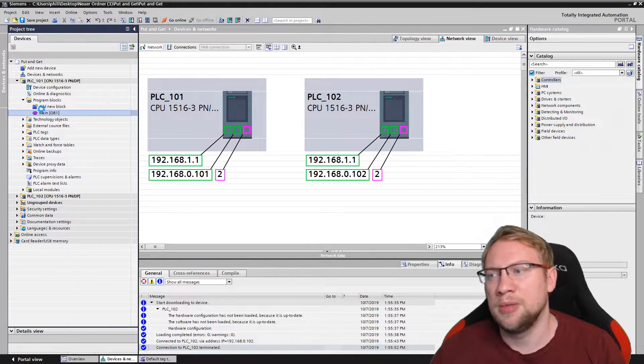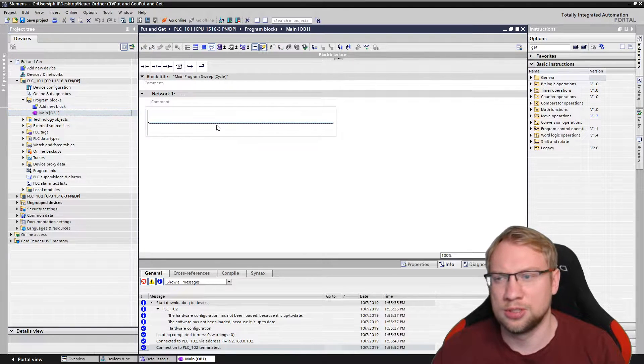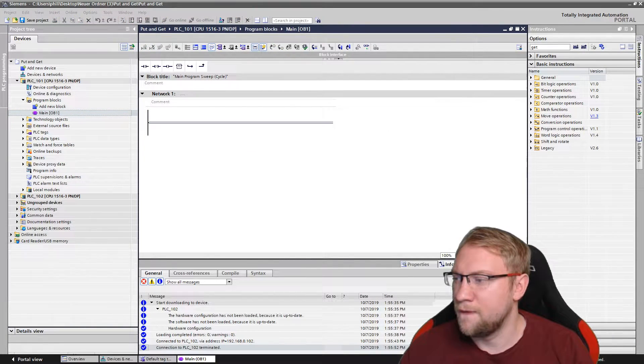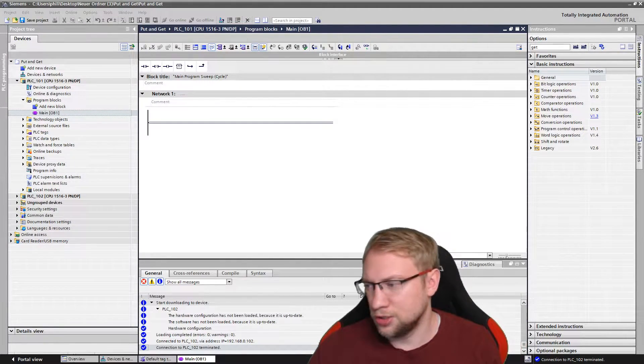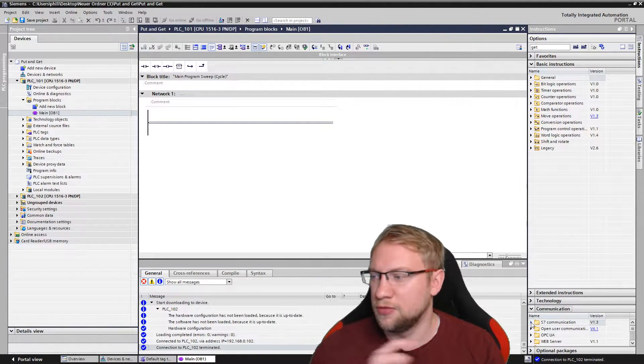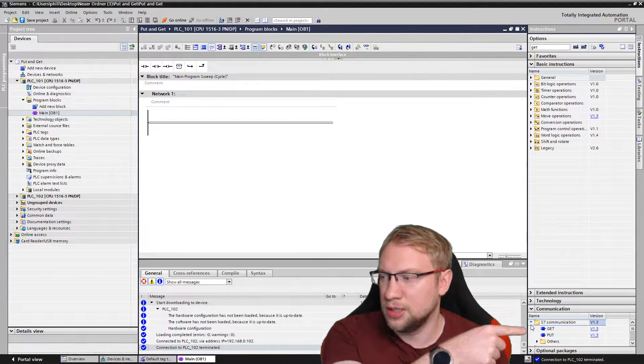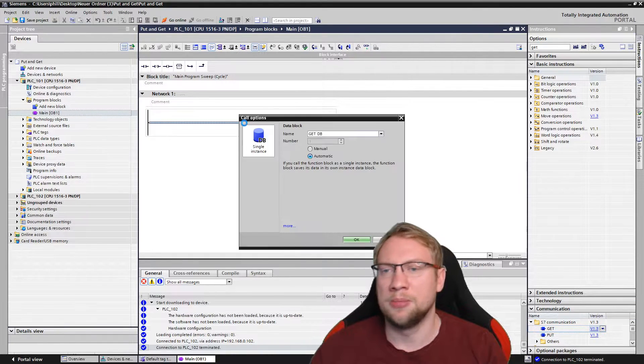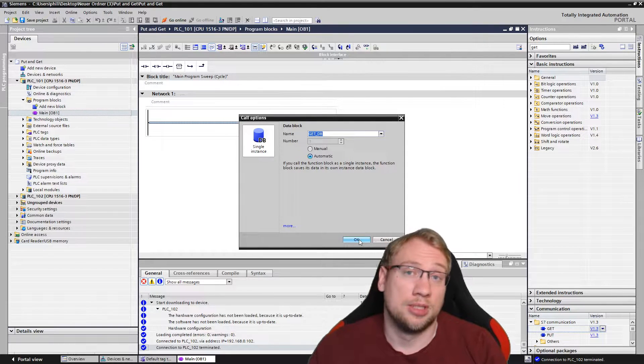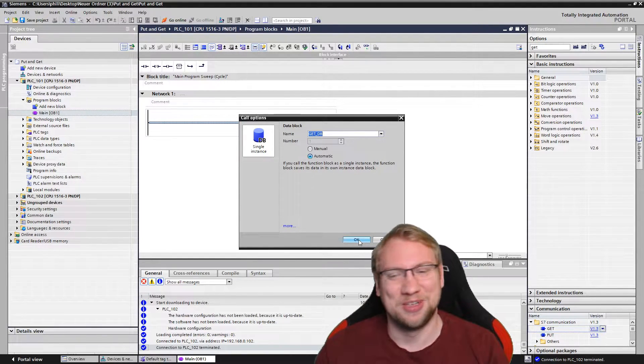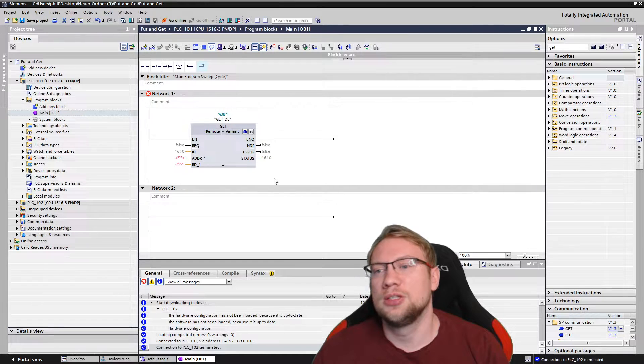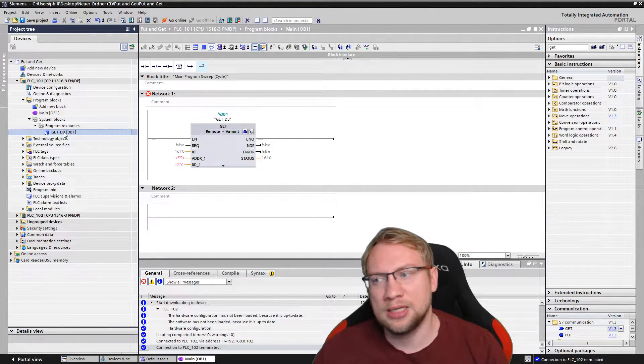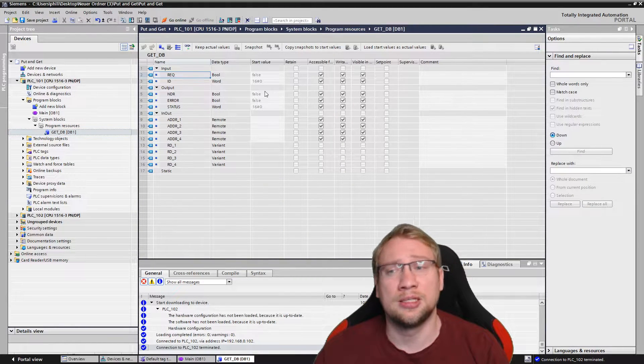Now let's get to the GET command. In the main function — you can also create a new function — search in the Instructions panel on the right side under Communication, then S7 Communication, and there you have GET. I can take GET and put it in my main function or anywhere in your program. It needs an instance data block because it is a function block.